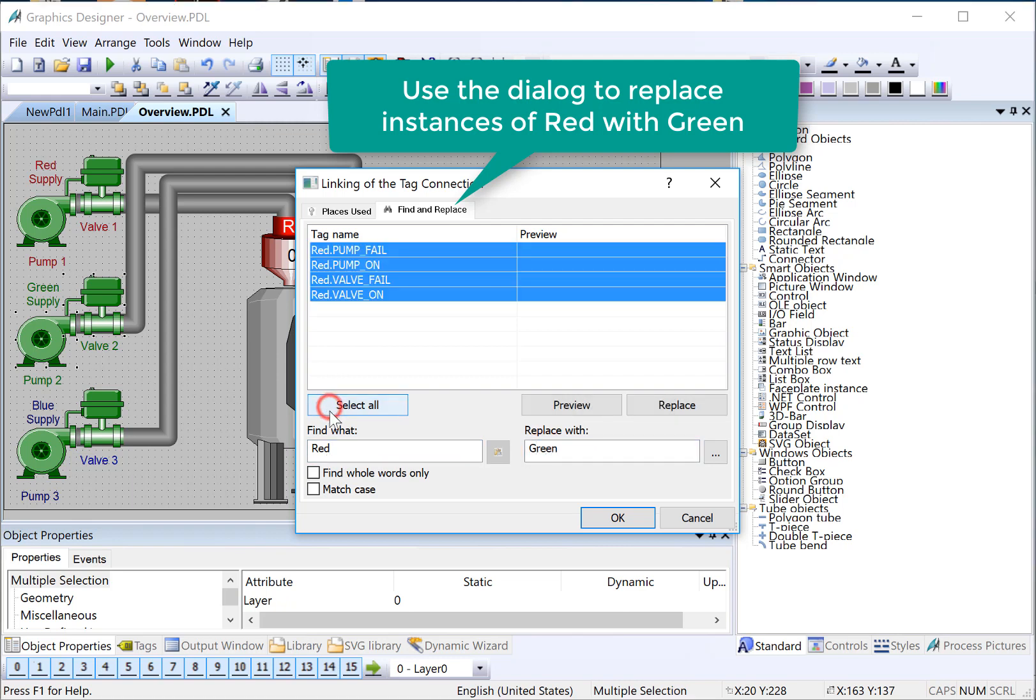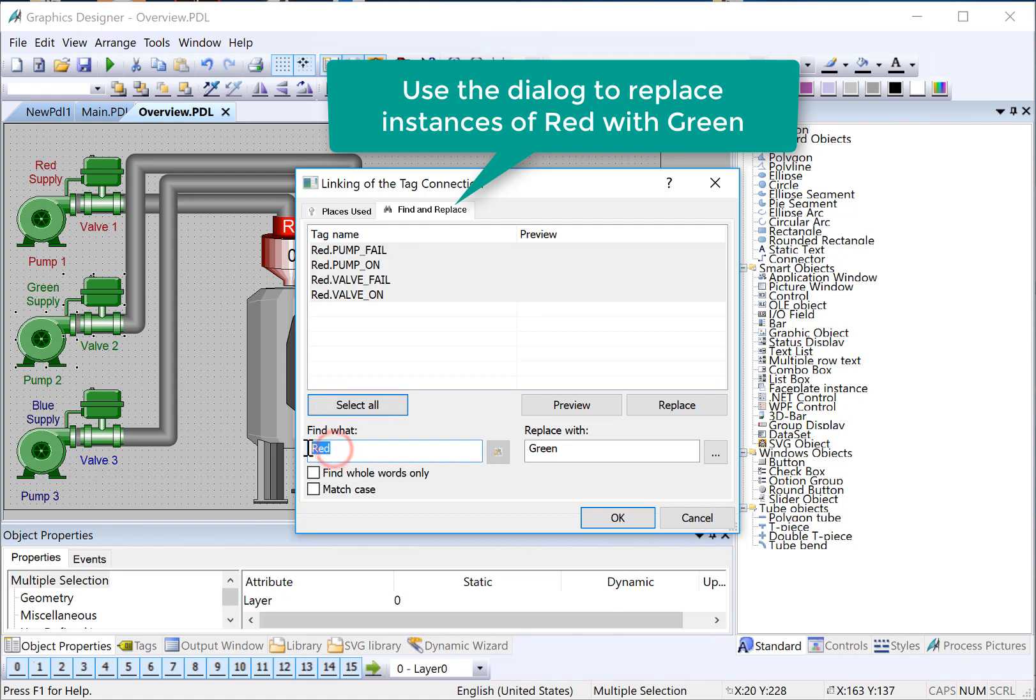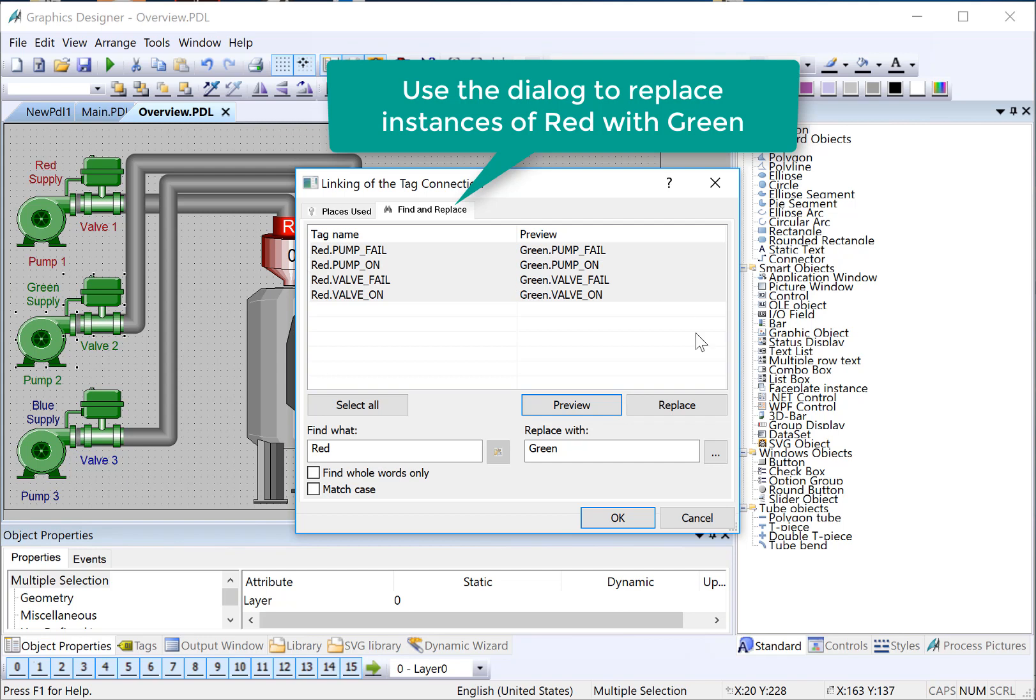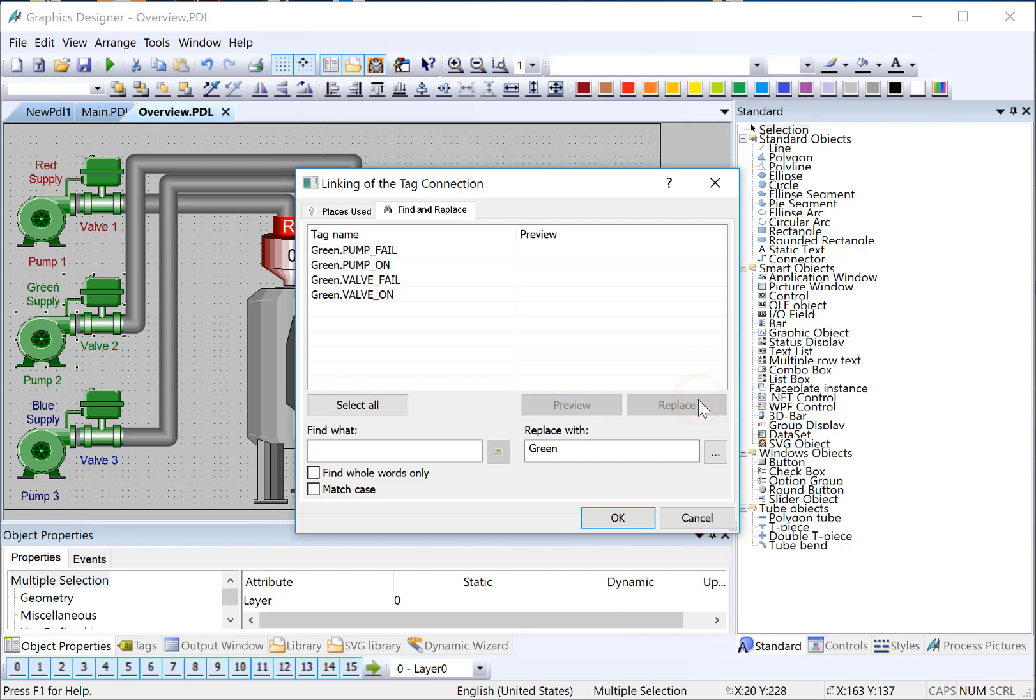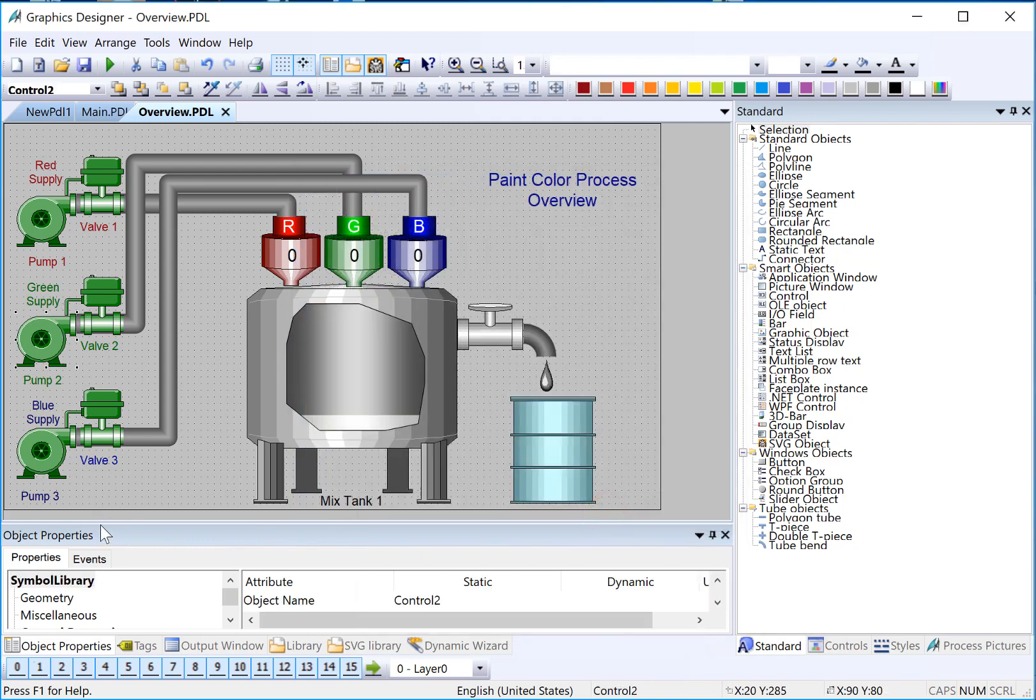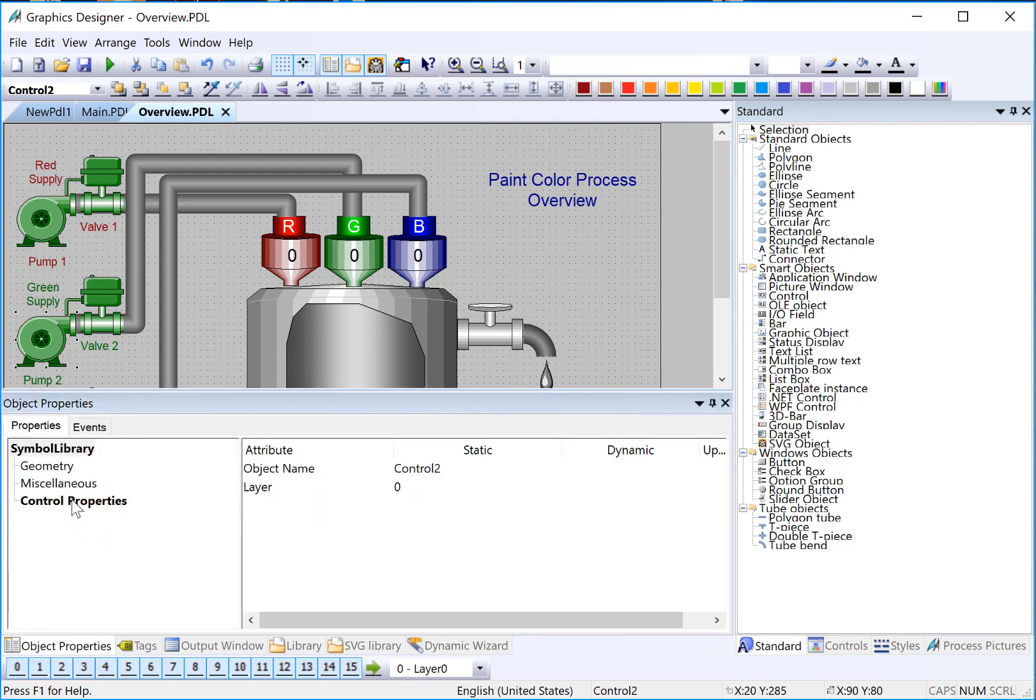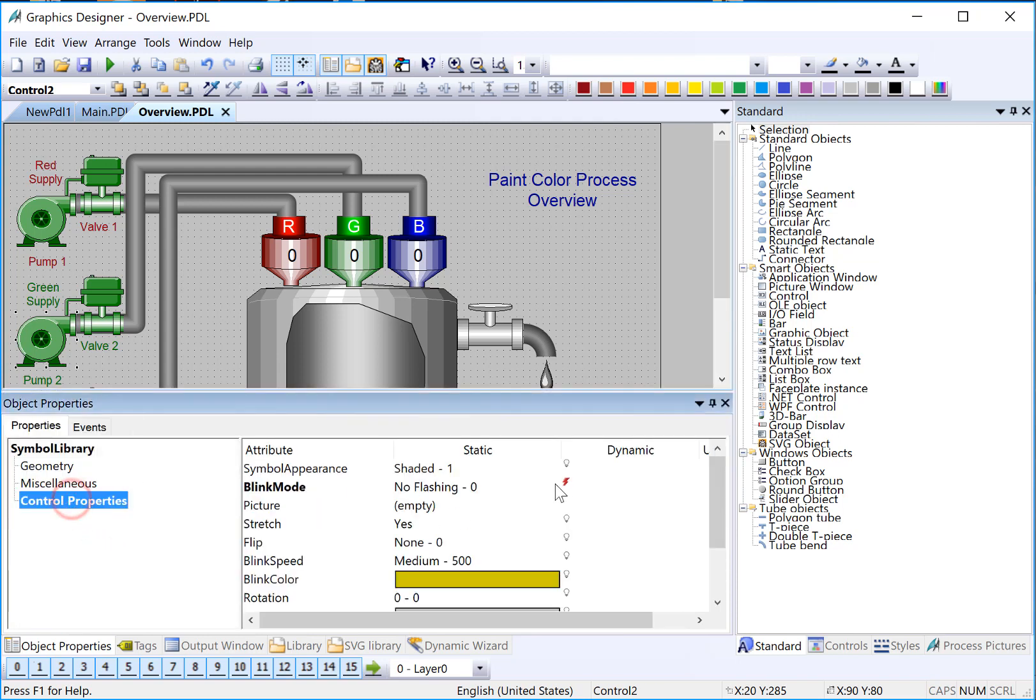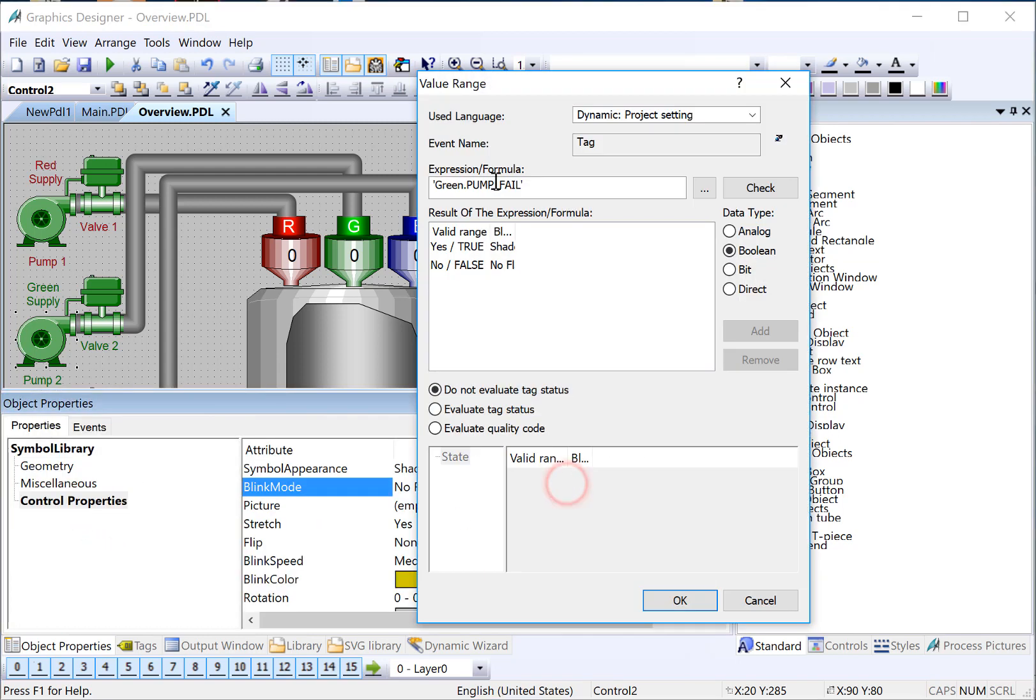So I just choose Select. It will find everything that meets this criteria, and then if I hit Preview, you can see, okay, it's going to replace red dot pump fail with green dot pump fail, and so forth and so on. That looks good. Now this is important. You have to hit Replace. And then you'll notice that now everything here is pointing to green. If I click OK, if I just go back and look at the pump and open the dynamic dialog, you can see it has been replaced.